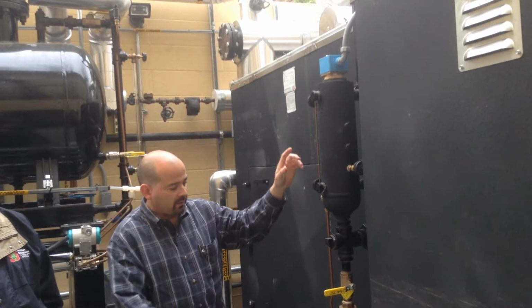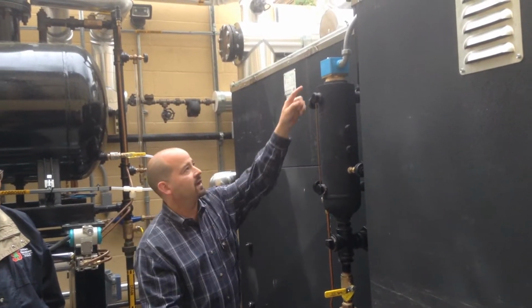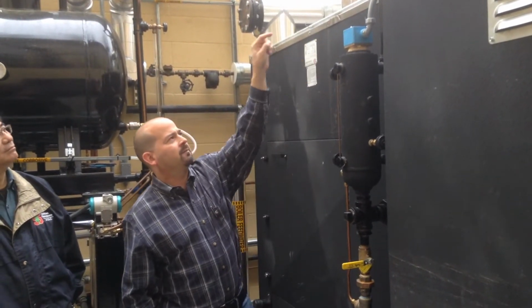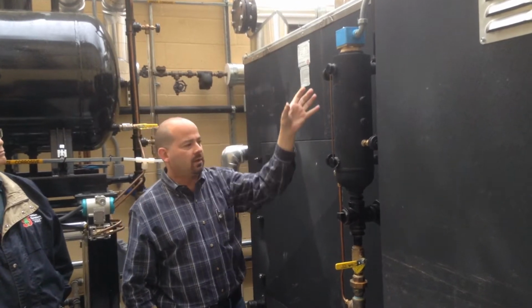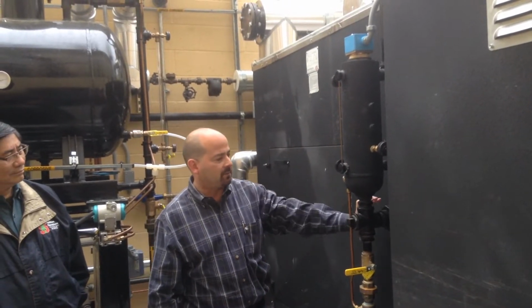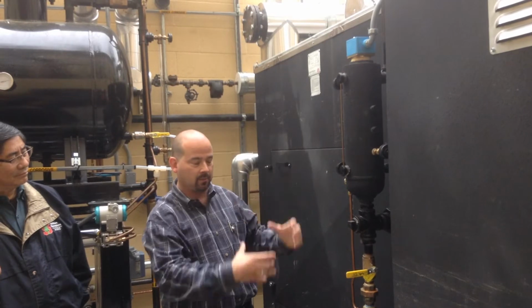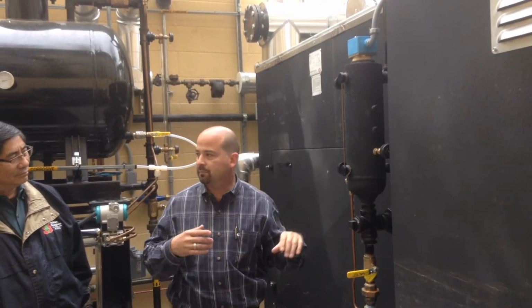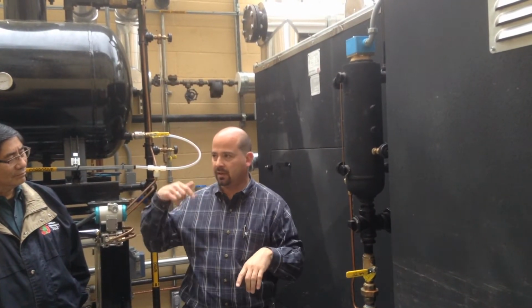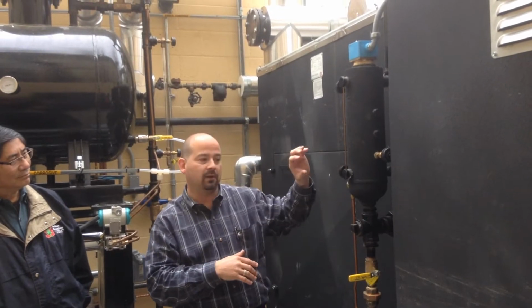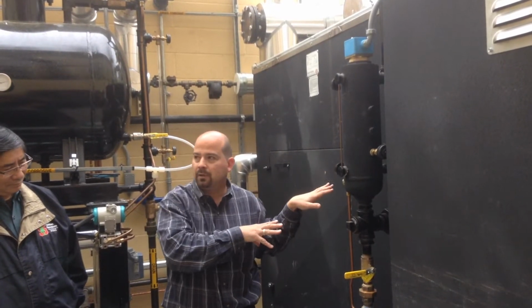And then this is what we call your equalizing line here. So you've got a 1-inch pipe that goes into the top of the steam drum. You've got your water column. You've got this pipe that goes into the downcomer on the boiler. So again, it's basically like the principle of a U-tube design, like on here. What's happening here is what's happening in the boiler.